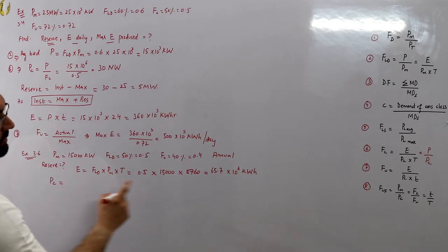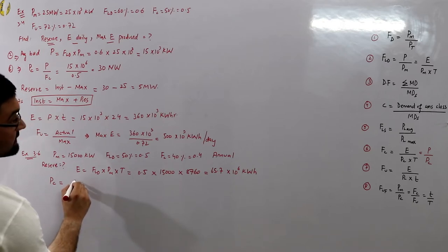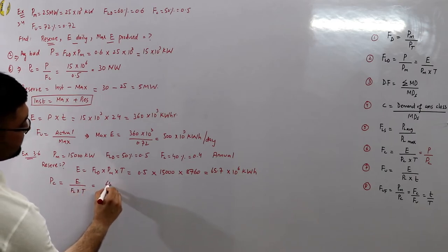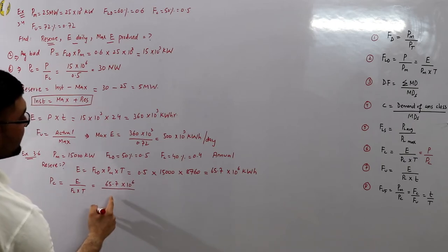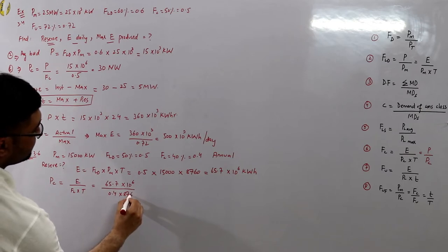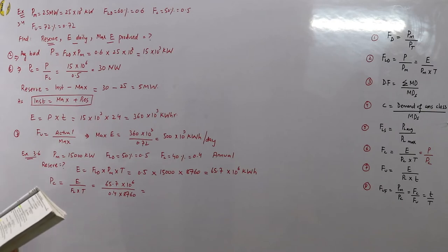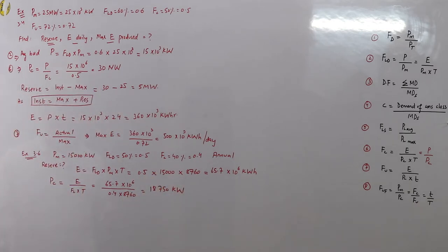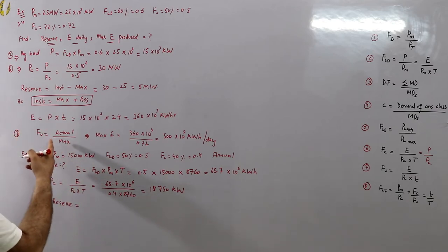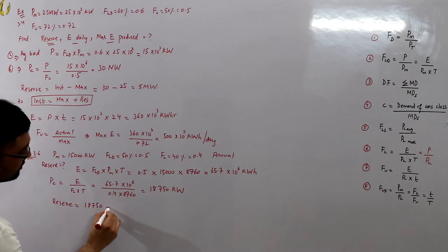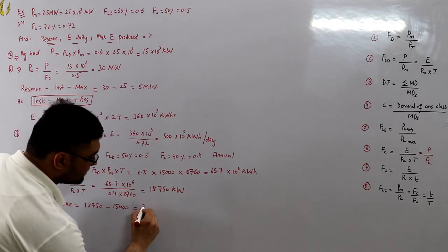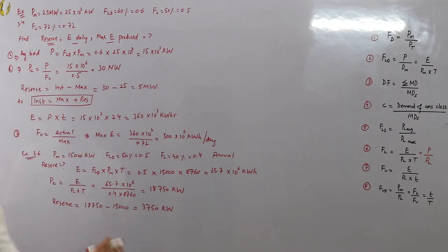Installed capacity PC = E ÷ (FC × T) = 65.7×10⁶ ÷ (0.4 × 8,760) = 18,750 kilowatts. The reserve capacity = installed capacity − maximum demand = 18,750 − 15,000 = 3,750 kilowatts.